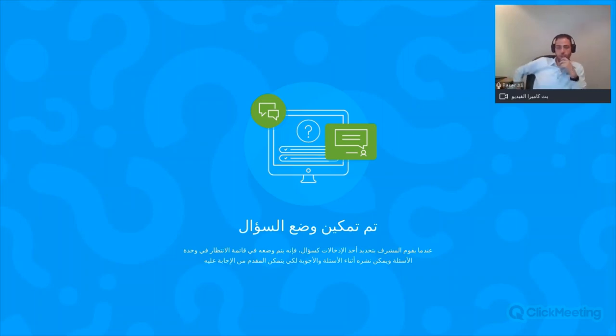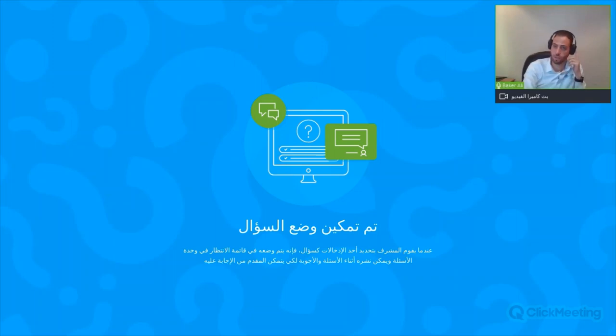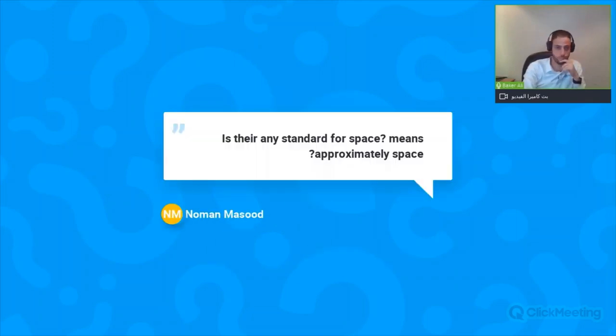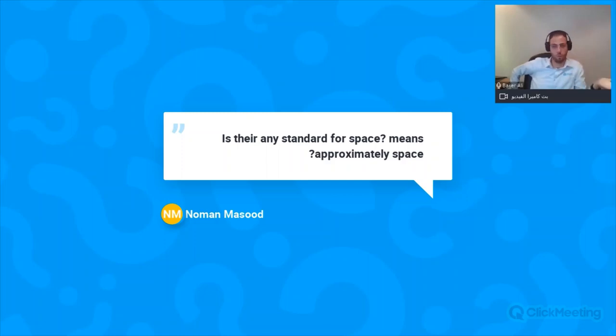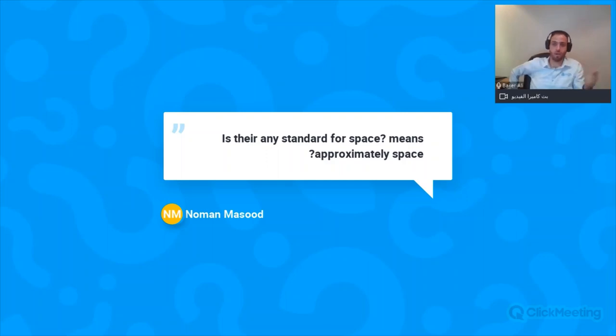That's it for today's presentation. Now we can start addressing questions. The first question: is there a standard for the space around the generator? The minimum is one meter around the generator on all sides — one meter from the front, back, right, and left — and at the top of the generator, a minimum of two meters. More space is better.